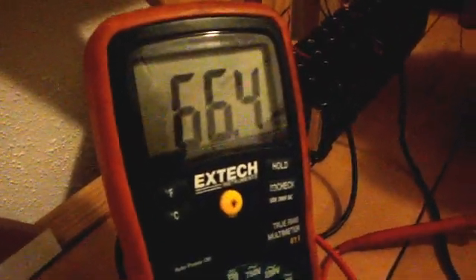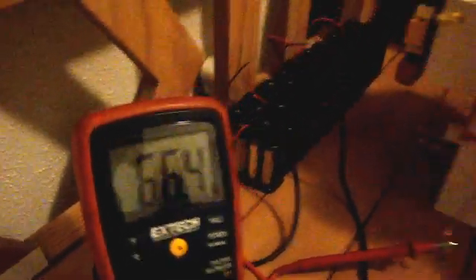Now let's switch this over to measure the resistance. 66.4 ohms. So with 66 ohms and approximately 85 volts, we're only drawing 100 milliamps. Why? Because it takes time for the current to rise, and you have the back EMF of the rotor.